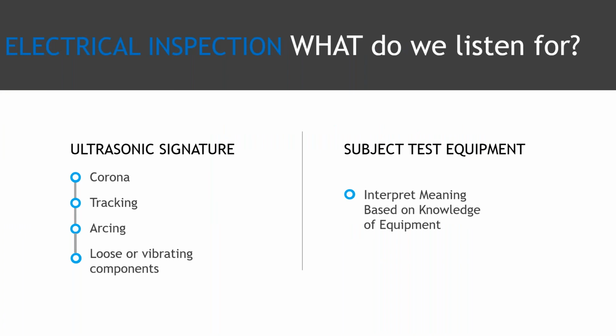So what do we listen for? I mentioned we're going to listen for anomalies. Typically, the 3 types of things we listen for: corona, tracking, and arcing. We can also listen for loose or vibrating components. And when I say subject test equipment and interpret the meaning, you can't really determine what those sounds are until you understand the components of that particular asset.